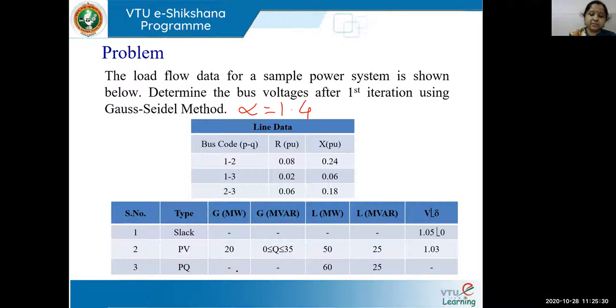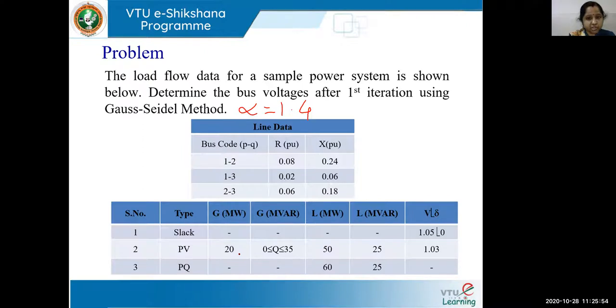Note that in this problem the generator and load values are not given in per unit but in megawatts and MVAR, while voltage is given in per unit. So first we convert to per unit. If the base is not mentioned, assume it as the highest value among the given data or consider 100 MVA. For this particular problem, I have taken 60 MVA as the base value. Let us see how the Y bus looks for this network.